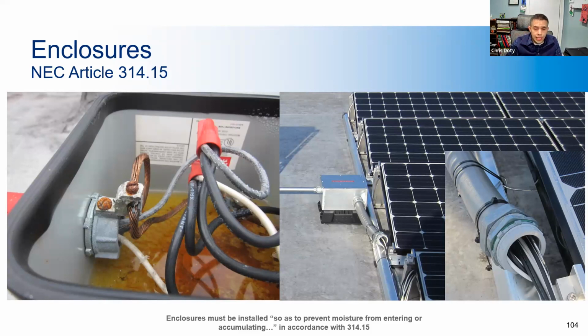And on the right, these are the same place. So this is on the far right, it's just a close up of right here. But this is a flat roof with panels installed on it. And you have the conduit that comes out of the box and it's bent up to get over this rail. And what that does is, if it ever rains, the rain will get in that conduit and it'll just go all the way down right into the enclosure. So it basically acts as a highway for water to enter the electrical enclosure, which again you want to avoid.